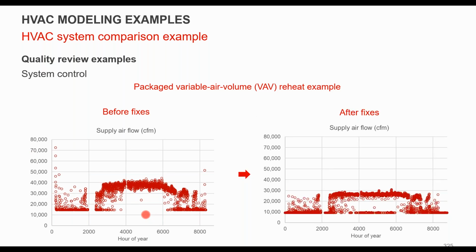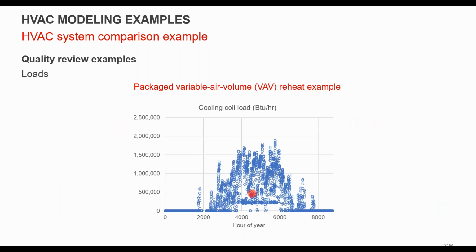What does it look like in your supply airflow? Once you made the fixes here, you're getting rid of all of these crazy hours when the system is oversizing pretty drastically to try to heat the building back up during that warm-up period. Sam, you've got a couple comments.